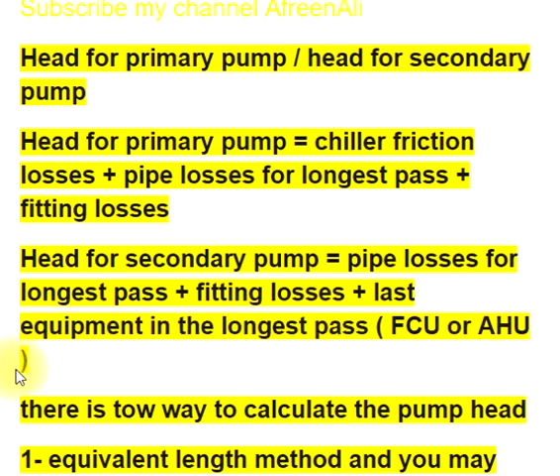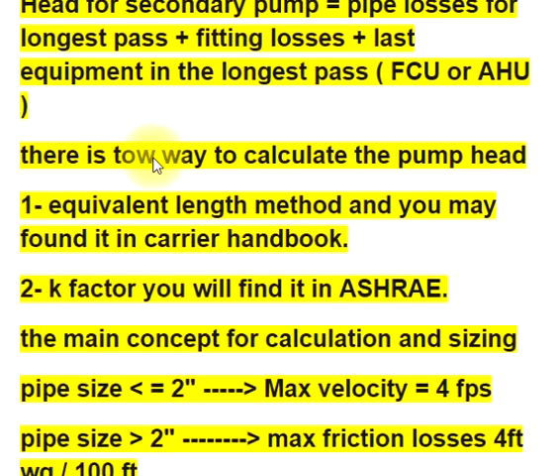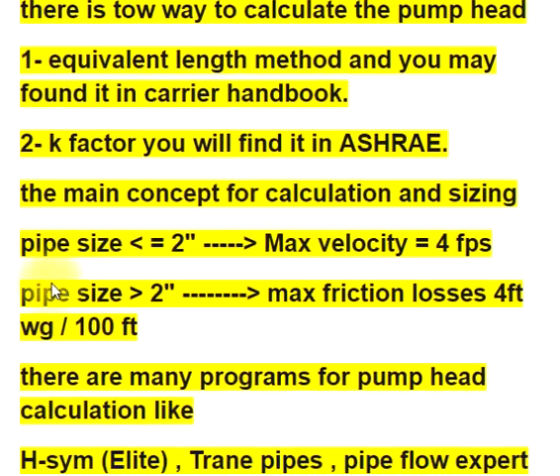There are two ways to calculate the pump head: the equivalent length method, found in the Carrier Handbook, and the K factor method, found in ASHRAE. The main concept for pipe sizing: max velocity equals 4 fps, and max friction losses equal 4 feet WG per 100 feet.